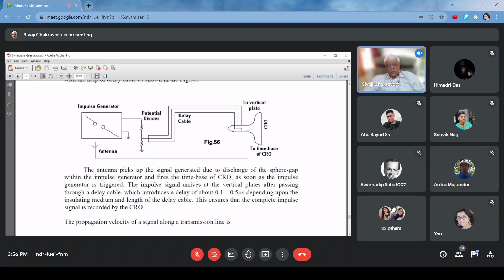So the antenna signal will come almost at the speed of light, whereas the impulse signal comes through the delay cable, where the propagation speed is only about 60 to 70% of light. Depending on the cable length, we get a certain delay, ensuring that the x-axis fires before the y-axis. This is called delay cable technology, and you can see how incorporating a simple cable lets us synchronize the recording operation.